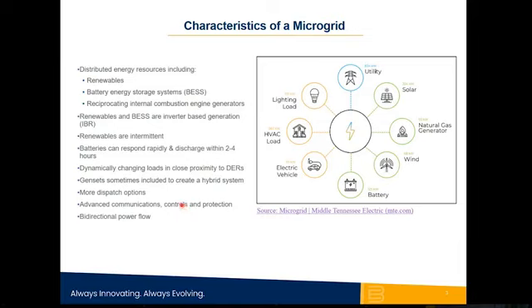And the way that a microgrid is protected is a bit different from the way that traditional protection is done, because, for instance, a synchronous machine can typically provide 8 to 10 times its rated current to support a fault and clear the fault, whereas BESS systems do not provide as much fault current. And as a result, the protection settings need to be lowered if you're now protecting a microgrid that's disconnected from the grid where there aren't any synchronous machines. So different protection settings need to be active at different times, depending on the configuration of the microgrid, whether it's grid connected, not grid connected, depending on which resources are operating.